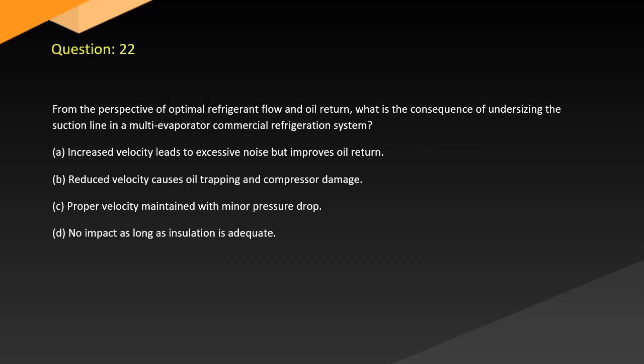Question 22. From the perspective of optimal refrigerant flow and oil return, what is the consequence of undersizing the suction line in a multi-evaporator commercial refrigeration system? A. Increased velocity leads to excessive noise but improves oil return. B. Reduced velocity causes oil trapping and compressor damage. C. Proper velocity maintained with minor pressure drop. D. No impact as long as insulation is adequate.